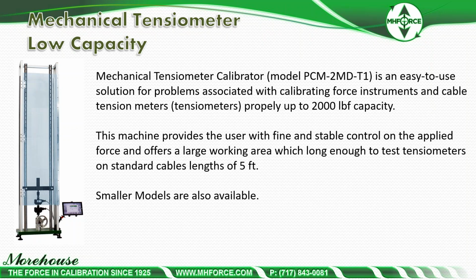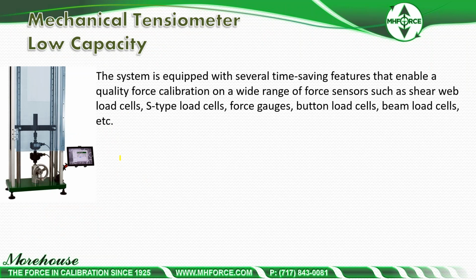We do have a solution. We built a mechanical tensiometer calibrator. It's a modified PCM. It goes to 2,000 pounds. It's got 5 feet in length. And we also have smaller models if the 5 foot is too long. Very tall machine. What you'll see different about this is this safety glass here. Hey, cables break. We know cables break, so this is made with the safety glass installed, load cells set up there at the bottom. It's equipped with several time-saving features that enable a quality force calibration on a wide range of force sensors. Shear, you can do everything you can do with the PCM.